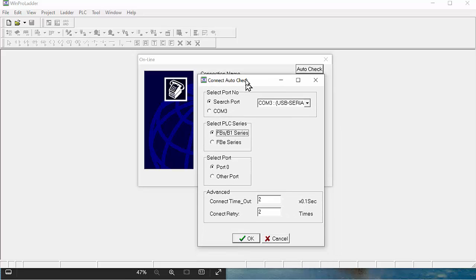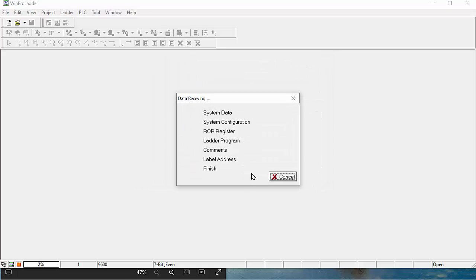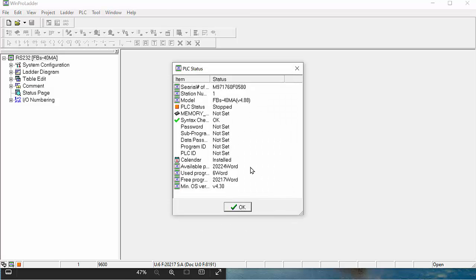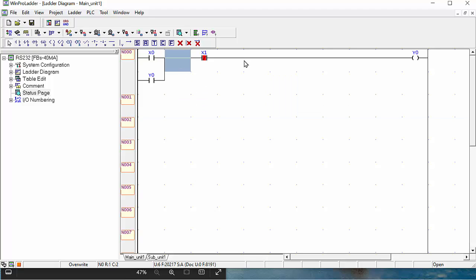When you click auto check, this message will be shown if your communication cable is completely connected with your PLC to the CPU, and then click OK. After this message, it shows: can connect to PLC port number COM3, station number one, baud rate 9600, data bits seven, parity even, connect now. Then click yes. So which program is in your PLC will be saved and come to the CPU. In my PLC, there's a small program for on and off control, and this is shown as per in the PLC.